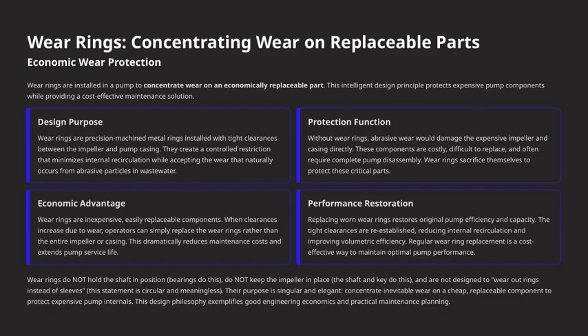One of the main advantages is economic. Wear rings are inexpensive and easy to replace. When wear causes the clearances to increase, operators can simply swap out the wear rings instead of replacing the entire impeller or casing. This approach significantly cuts down maintenance costs and helps extend the overall life of the pump. Replacing worn wear rings also restores the pump's performance. It reestablishes the original tight clearances, which reduces internal recirculation and improves the pump's volumetric efficiency. Regular replacement is a practical, cost-effective way to keep the pump running at its best.